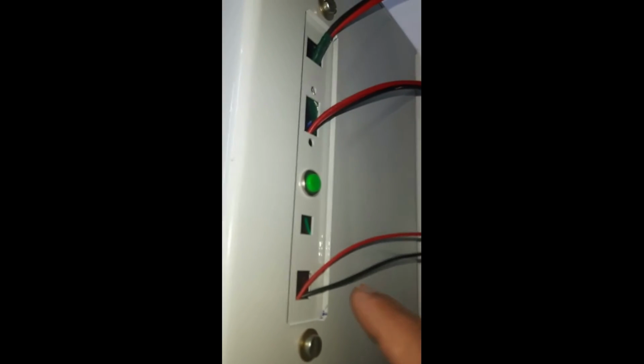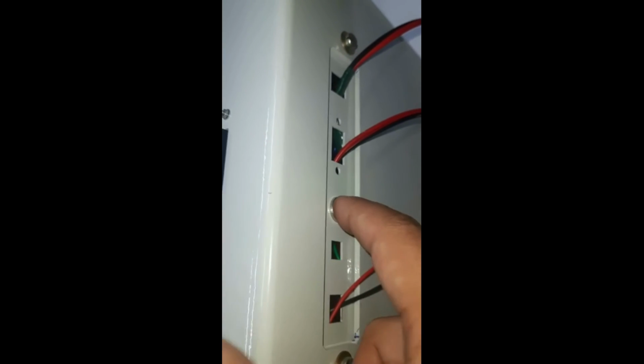Now we will see how to calibrate the oxygen sensor in this oxygen analyzer. So it's very simple. We just need to take it to an open area where you can expect a little bit of pure air, maybe less pollution, etc., if possible. Otherwise, just take it to an area where there's a good supply of ambient air. And all we need to do is just press the button, this green button, like this for 1 second, and let it go. And as you can see, this is collecting data from the oxygen sensor, thereby calibrating it. It will take about a minute.